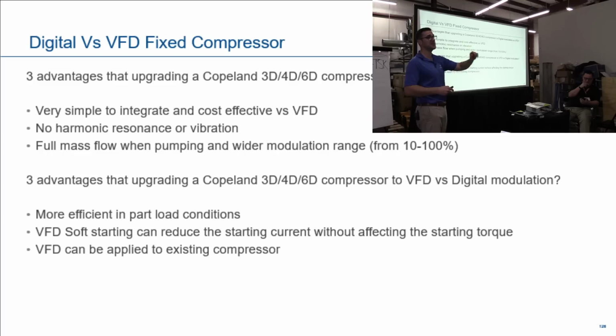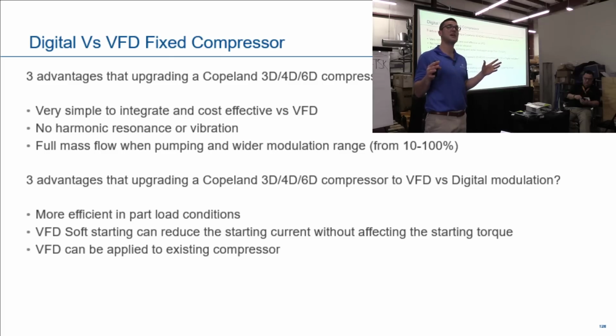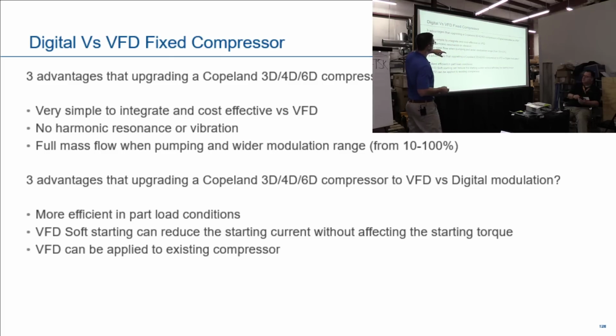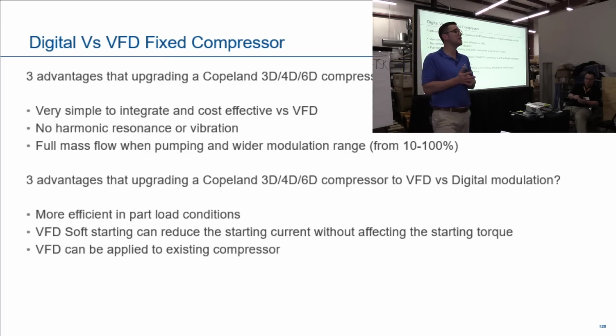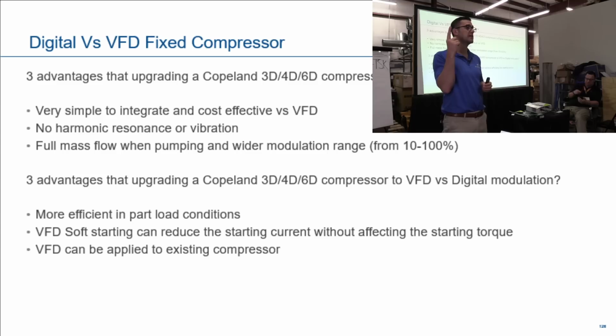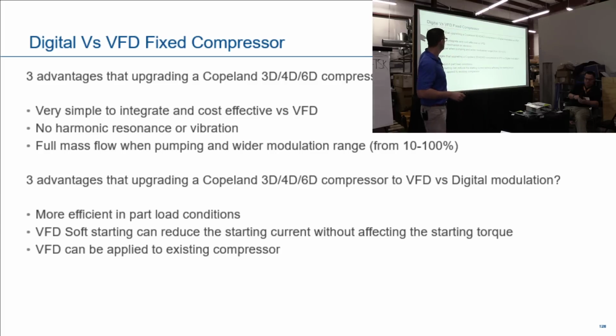So here's the big thing: digital versus variable speed compressor. I get this all the time. What's better? Is digital better or is variable speed better? Well, the advantage of digital is that it's very simple to integrate and cost effective. That's the big thing. We have lots of contractors putting drives on compressors, which is great, but only one guy can work on them. So at 2 o'clock in the morning, when a mechanic goes out and doesn't understand how to use the drive, they just bypass it. We see a lot of applications like that. So digital is more advantageous on the complexity side.